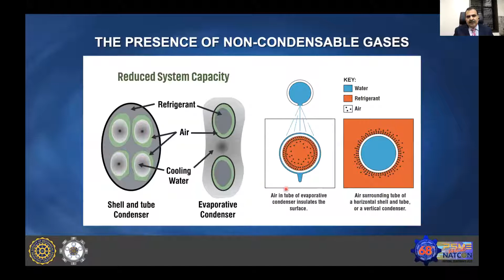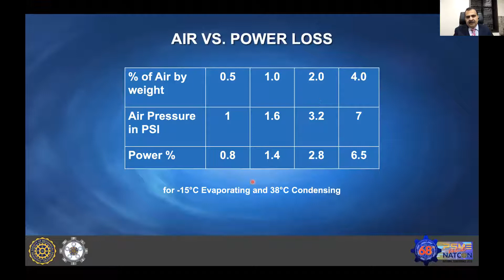If we ask how much air there is and what the power impact is typically: if we have 4% air by weight in our system, the pressure may increase by 7 psi, which will contribute almost 6.5% of the refrigeration plant power. Now, this data was calculated by the Association of Ammonia Refrigeration for minus 15 evaporating and 38 condensing. This may change when we have higher or lower evaporating temperatures.